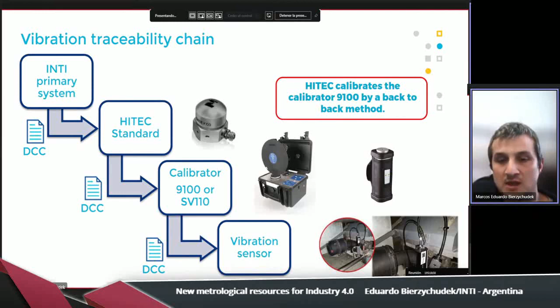So we don't calibrate just the calibrator. We calibrate the calibrator plus the multimeter. And they have to use it in this way because of the calculation we make, and in this way we reduce the uncertainty of the standard, because we are neglecting the uncertainty of the internal readout or the internal digitizer of the instrument.